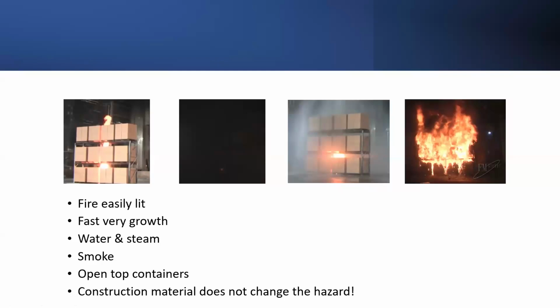In some of these systems, the flue spaces are closed. So again, if you think about the Ocado system, the AutoStore, the robots are actually running along what would be your flue spaces. The flue spaces are there for the heat to go up and activate your detection and suppression. And then the water uses the same flue spaces to come down to pre-wet and suppress. But again, that's all potentially impacted. We need to think about these things.